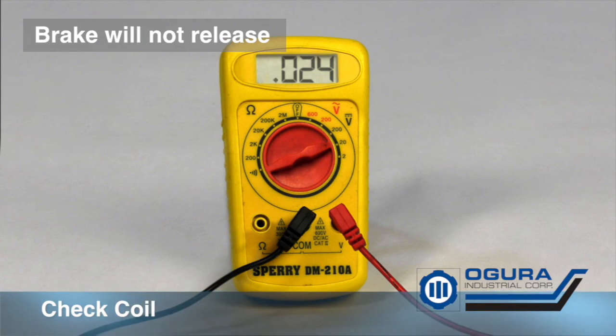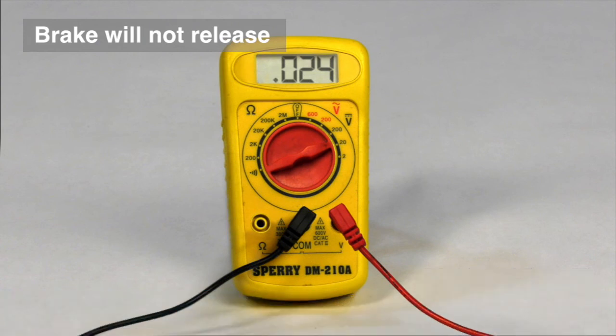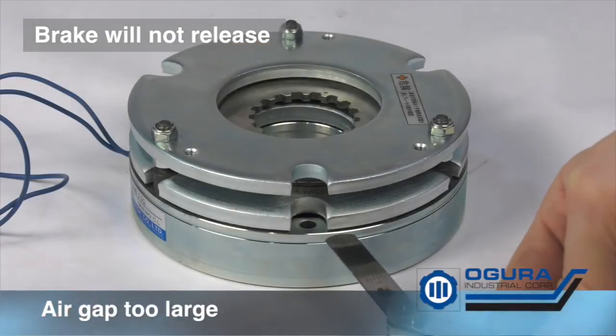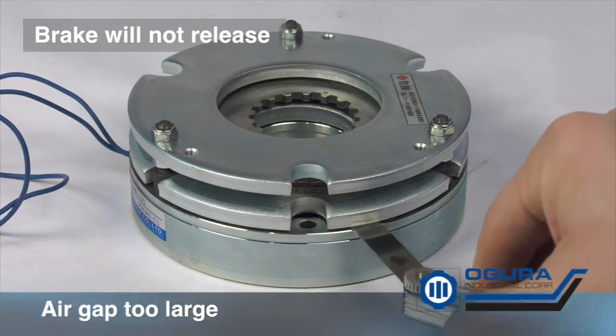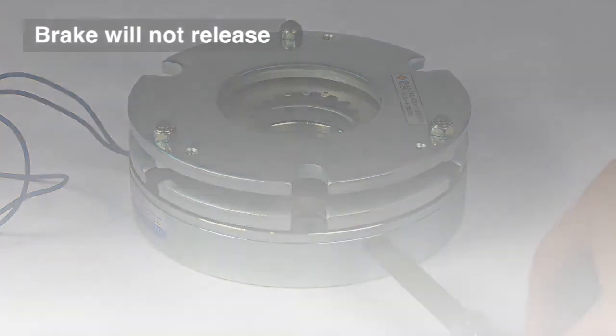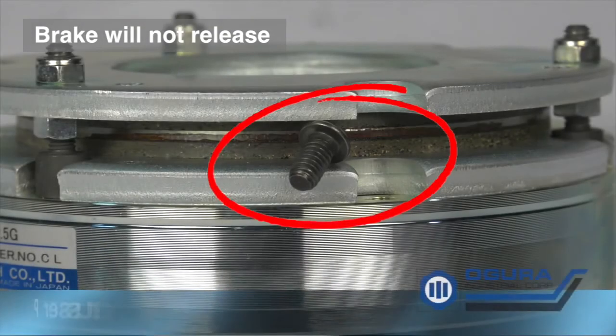Brake will not release. First, check if proper voltage is going to the brake. Check power supply and check leads going to the brake coil. Air gap too large. Brake friction material is worn down. Check air gap.